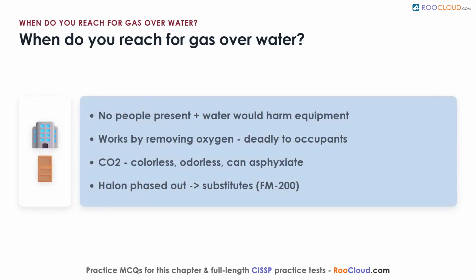When do you reach for gas instead of water? When people are not present and water would do harm. Gas systems smother fire fast and leave equipment undamaged, but they work by removing oxygen, which makes them deadly to anyone in the room. Carbon dioxide is effective, yet dangerous, since even a modest concentration can asphyxiate, and it is colourless and odourless, so it gives no warning. Halon starves the fire by breaking the combustion chemistry, but it harms the ozone layer and turns toxic at high heat.